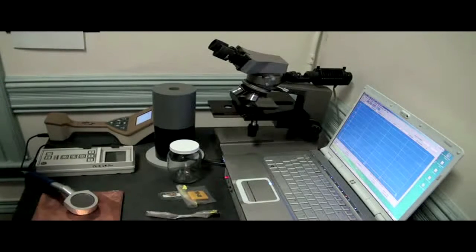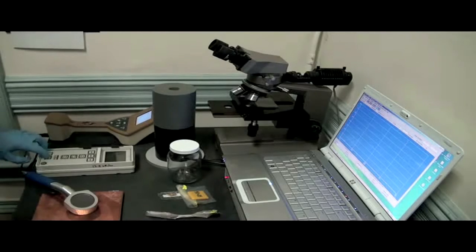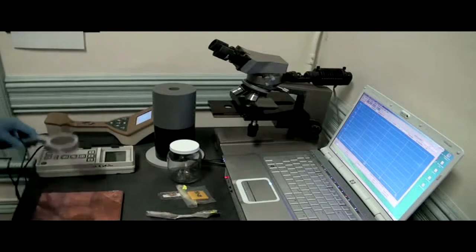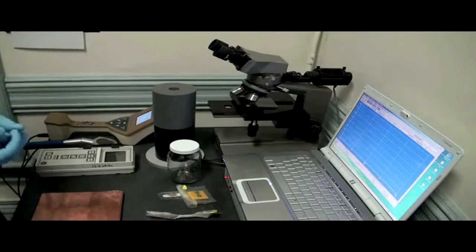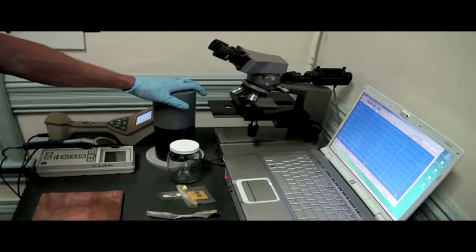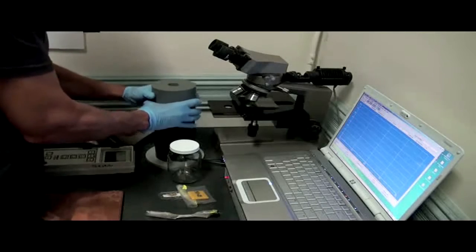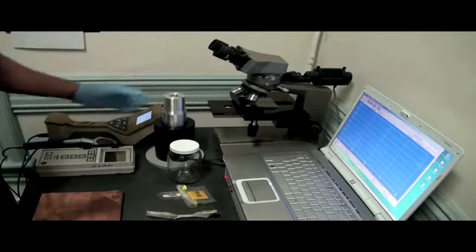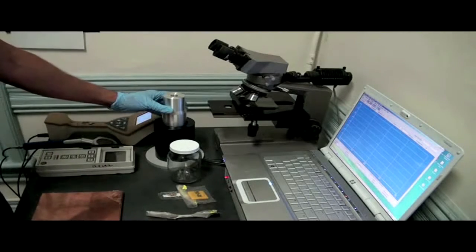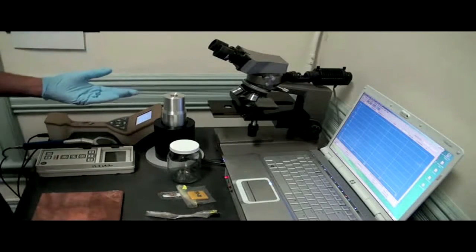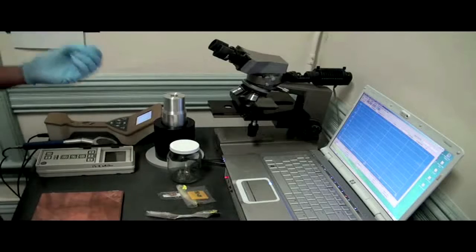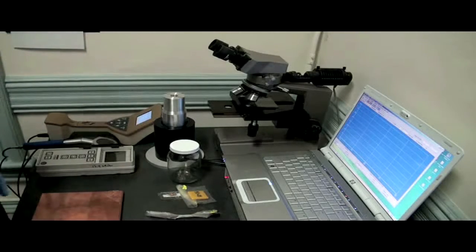For that we use a different kind of device. For that we actually use a gamma spectrometer. And what this does, we use a crystal, and the crystal actually will give off flashes of light when it's exposed to gamma rays. And we can actually see which isotope those gamma rays are from.